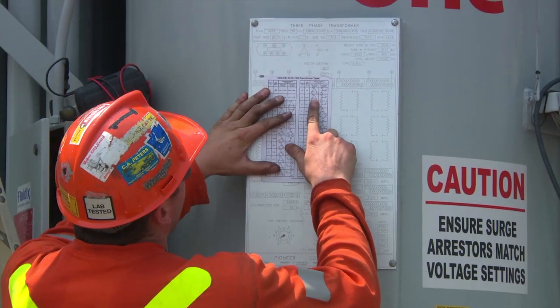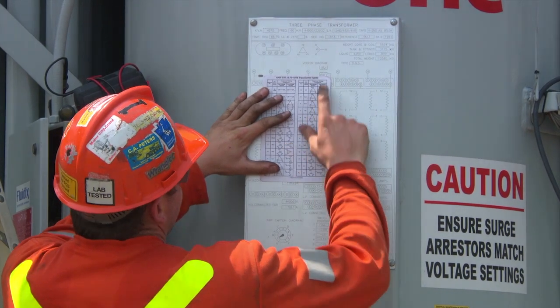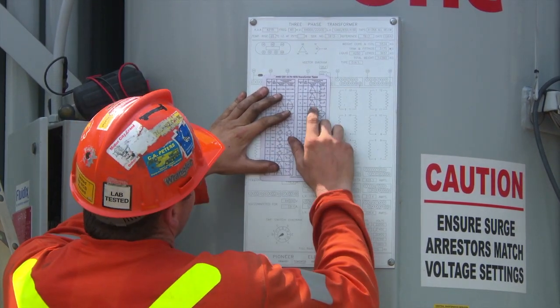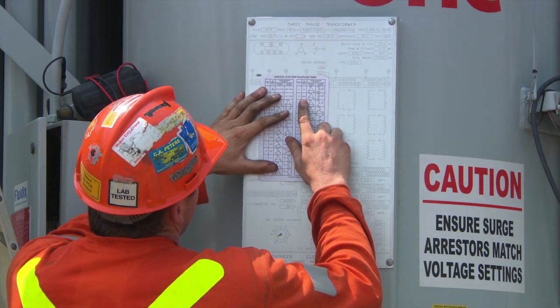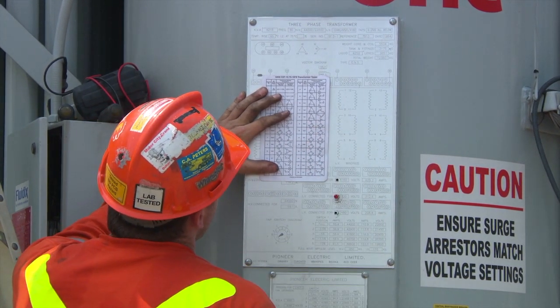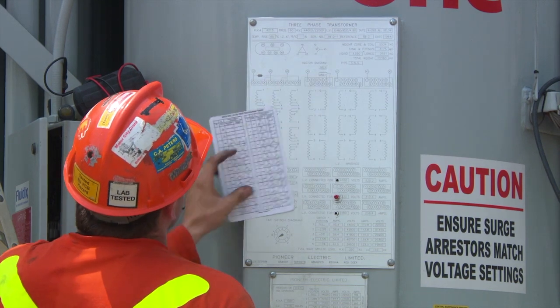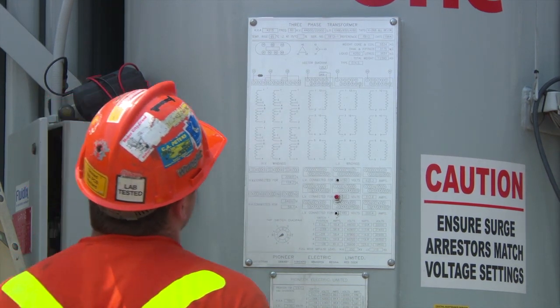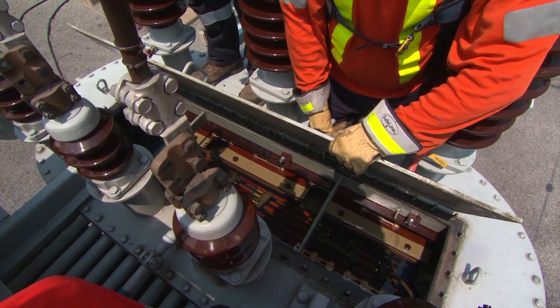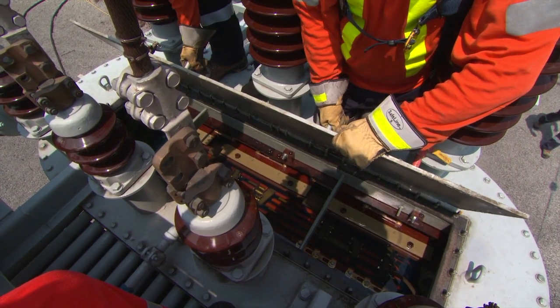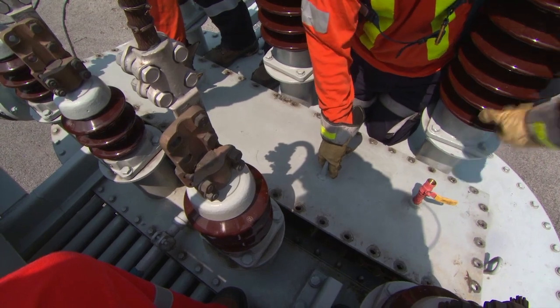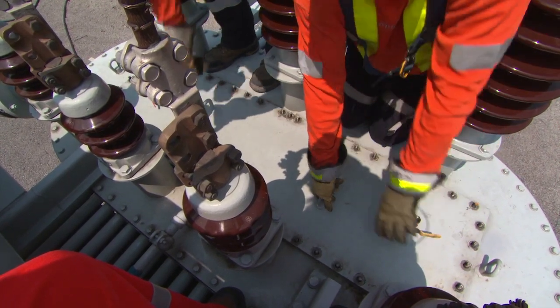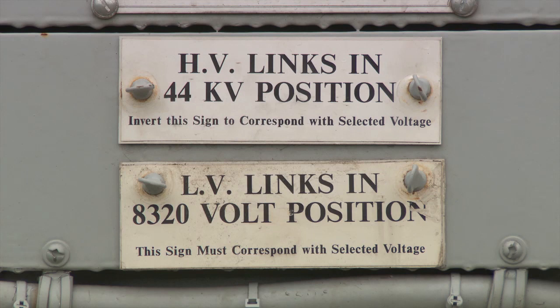Yep. The RME on ground will refer to the MUS transformer nameplate to determine what the link positions need to be to match the station voltage. The other RME will then remove the bolted connections using a wrench and turn the links to their required positions. Once the links are in the correct position, put the manhole cover back on and fill the main tank back up with oil. Change the low-voltage link position nameplate located on the side of the transformer to indicate what voltage link position the transformer has been left on.